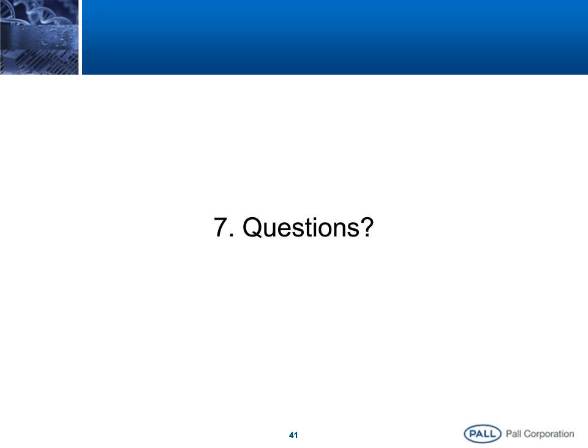And I'm just turning to some additional questions here. Can these units be used on Canadian mine fuel? Yeah, mine fuel, you'd be looking at a typical diesel flow. They'd be well suited to those types of application. Lubes was included in the question. Lubricating oils would typically be too heavy for use in the coalescers, but you could handle lubricating oil filtration in particulate removal mode quite effectively with these products.